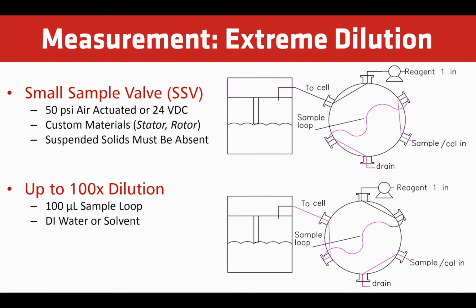In the event that a sample analyte is simply too high for us to do with a standard method given the amount of dilution that's required, we can offer what's called a small sample valve. This is simply a small sample loop in a manifold rotating valve, which is either air actuated or 24 volt motor actuated. We offer this with custom materials, depending on the application, for material compatibility. One thing that's important with the small sample valve, because it is a basic ceramic rotor and stator, is that we do not want any suspended solids present, because over time that will scratch it and damage the seals. But with this device, we can offer up to 100 times or more dilution capability. So if it's a very, very high range analyte, we can dilute it out and still use our methods, and then on top of this still do a DI water or solvent dilution.